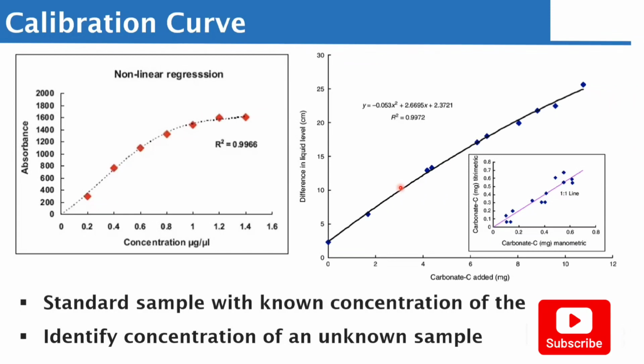It could be because that sample could be abnormally high or abnormally low, that is greater than what the analyzer can measure. Let me give you an example. If the analyzer can measure something like, let's say, between 5 to 20, the calibration curve generates the abnormally low, normal, and abnormally high. But there is how far low it cannot go, and there is how far high it cannot go as well.